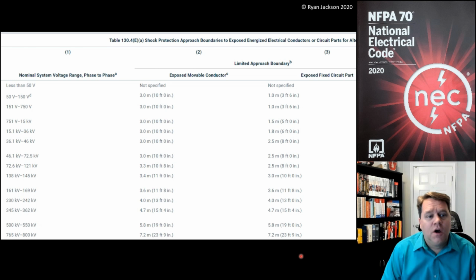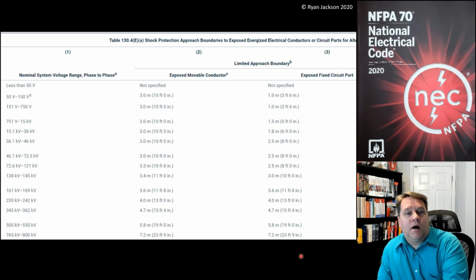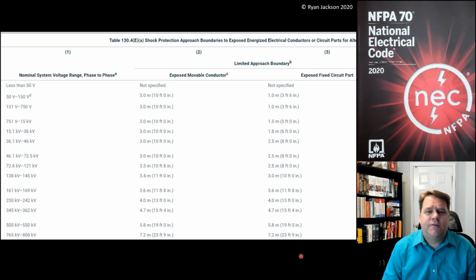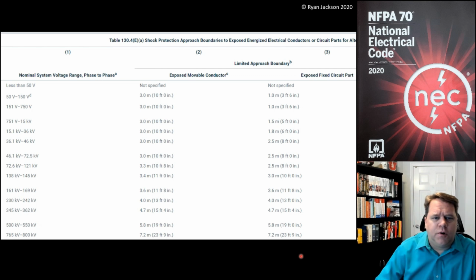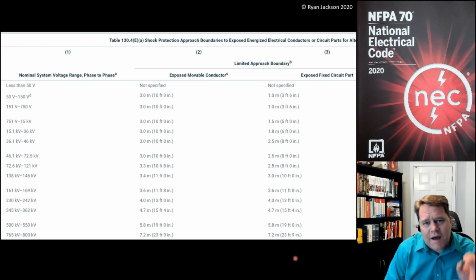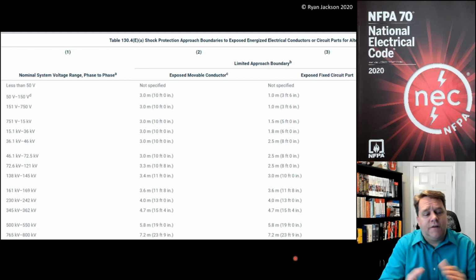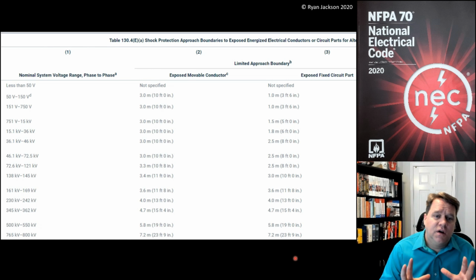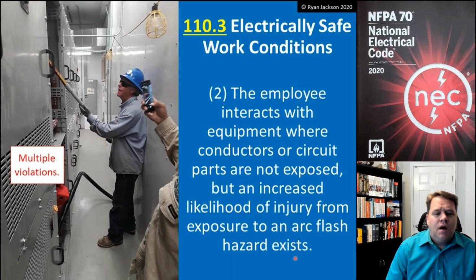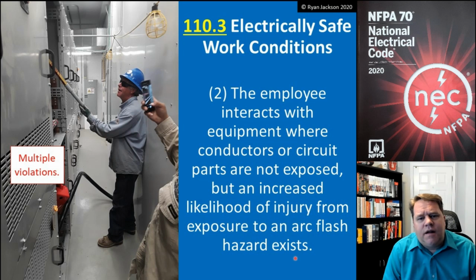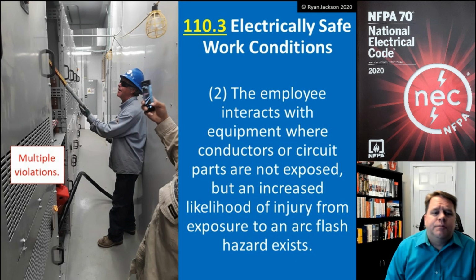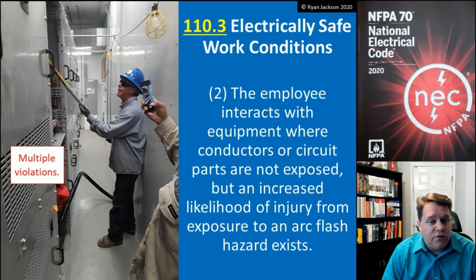So it's 3.5 feet for voltages of 50 volts up to 750 volts line to line. And for most of us, that's where we spend most of our time, right? 480 volts, 120/208, 120/240. So for most of us, the limited approach boundary is 3.5 feet. So I have to have an electrically safe work condition if I'm within 3.5 feet of exposed live parts. If I keep reading, I also need to have an electrically safe work condition if the employee is interacting with equipment where conductors or circuit parts are not necessarily exposed, but an increased likelihood of injury from exposure to an arc flash hazard exists.